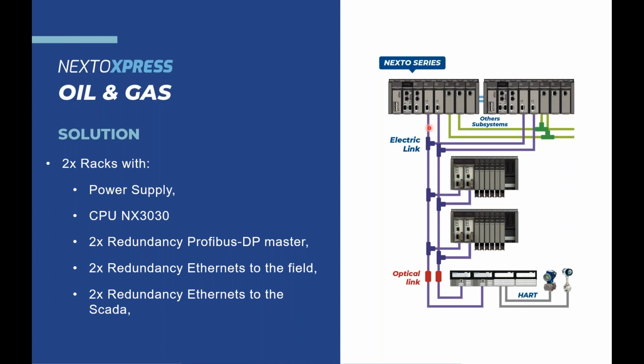Normally we see one active and one inactive, so one standing by, just ready to act in any problem. In our case, we have both networks acting. So we have network A active, and network B also active. What is the difference from the other scenario?